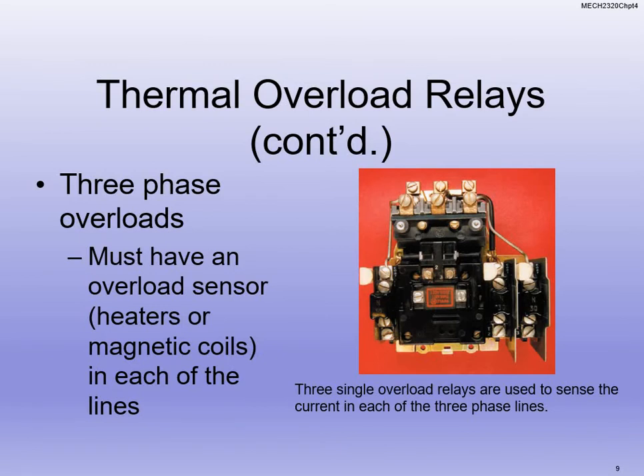Think about a motor. We've got a conveyor, and the motor is running the conveyor, and there's something too heavy on the conveyor, but the motor is going to pull in as much current as it possibly can to try and keep that conveyor going, because that's all it knows that it can do. And when that motor pulls in so much current but still can't move, you begin to start frying everything on the inside.